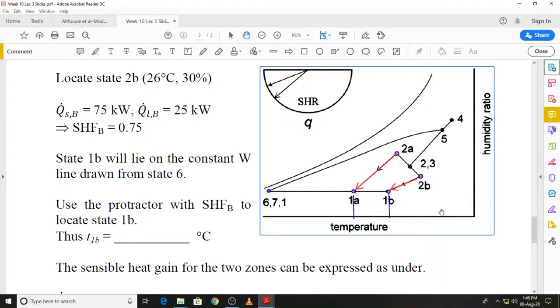You can see that on the psychrometric sketch I have shown these points that we have located. We started with state 6, located state 2A, used the sensible heat factor, located state 1A, found out the dry bulb temperature at state 1A. Then similarly you can see that we can locate state 2B because we are given the dry bulb temperature and the relative humidity. Then the sensible heat factor is also worked out from the sensible and latent loads. Once we have got those, we will use the protractor and then locate state 1B, and at that state we can then find out the dry bulb temperature. So that is the way we can locate states 1A and 1B.